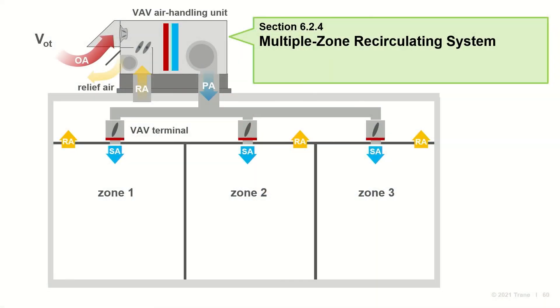For the third type — a multiple zone recirculating system — the calculation is more challenging. For our example, one VAV air handling unit serves all zones on the floor, with a VAV terminal in each zone to vary airflow or reheat. In this type of system, the primary air leaving the air handler is a mixture of outdoor air and air recirculated from all zones.